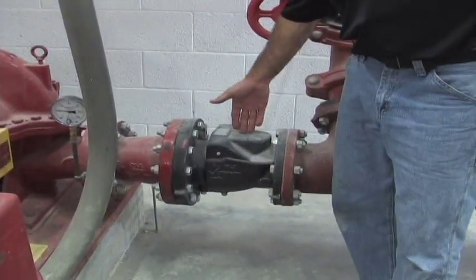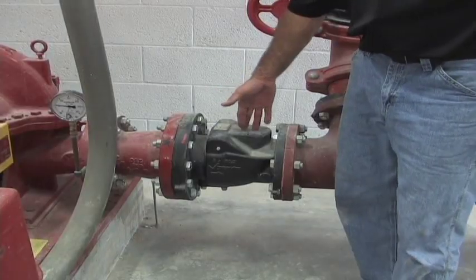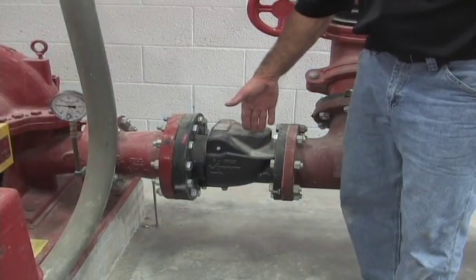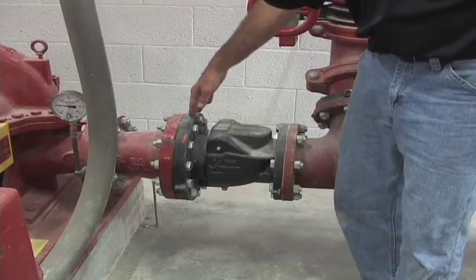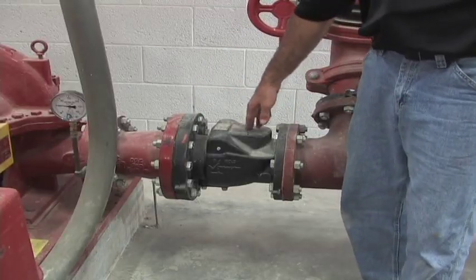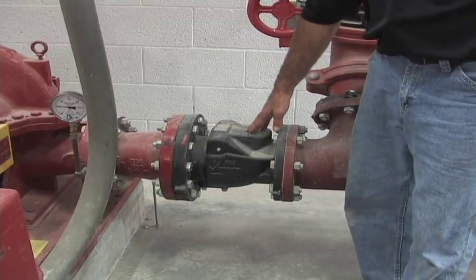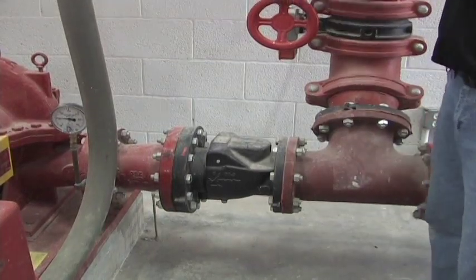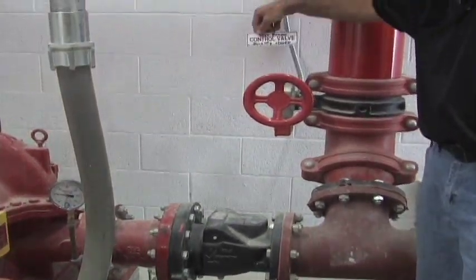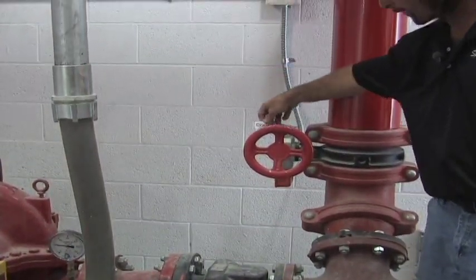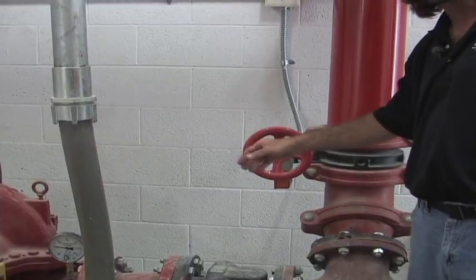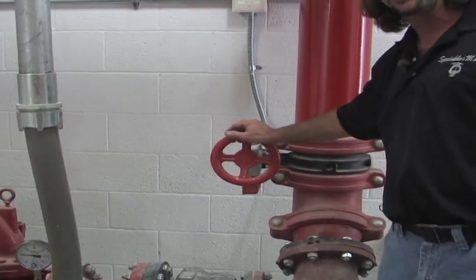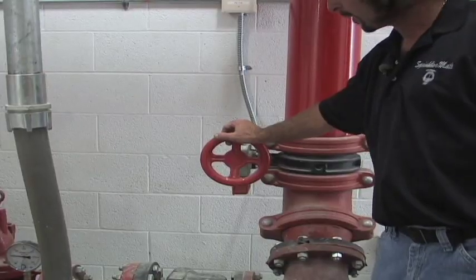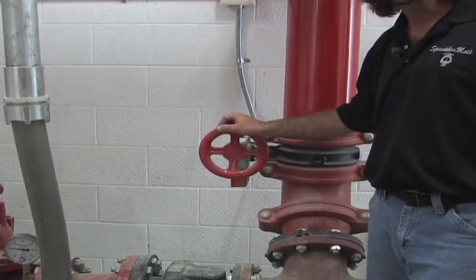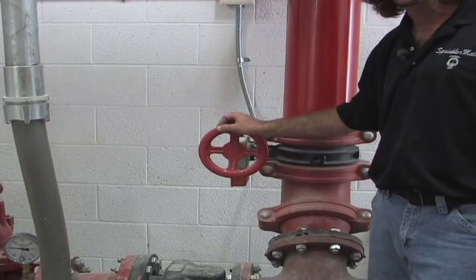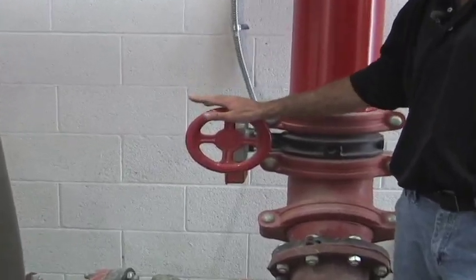Over here, we have our one-way directional check valve. You have city pressure on the supply side, and on the discharge side, you have whatever the fire pump discharge is. We have our control valve. This is for our test header. This valve will only be used once a year, and it's in the normally closed position. We use this valve once a year whenever we do the fire pump performance flow test. Used once a year, and it's normally closed.